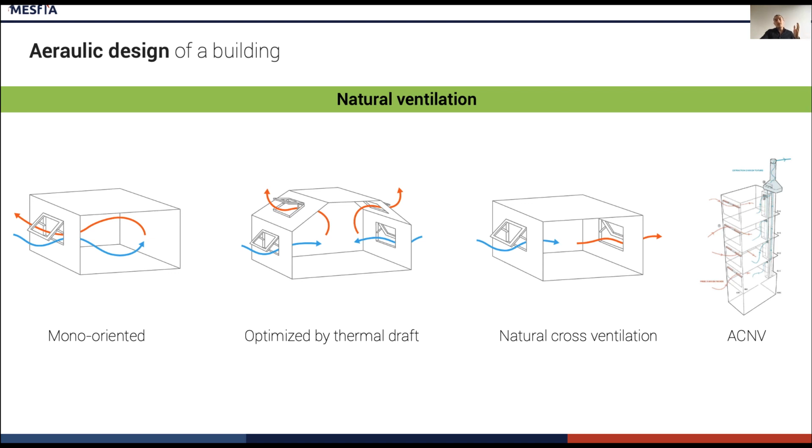Assisted and controlled natural ventilation, ACNV. The randomness of the climate is a main drawback of natural ventilation. It is thus a question of compensating for this weakness by reinforcing the system with natural devices, allowing us to increase or to control the flows. At the entrance, it can be the degree of opening of the window or adapted self-regulating vents. At the outlet, one can imagine registers controlled by the airspeed in the chimney, the wind by venturi effect or by a static fan, or the sun which artificially superheats the air in the duct.